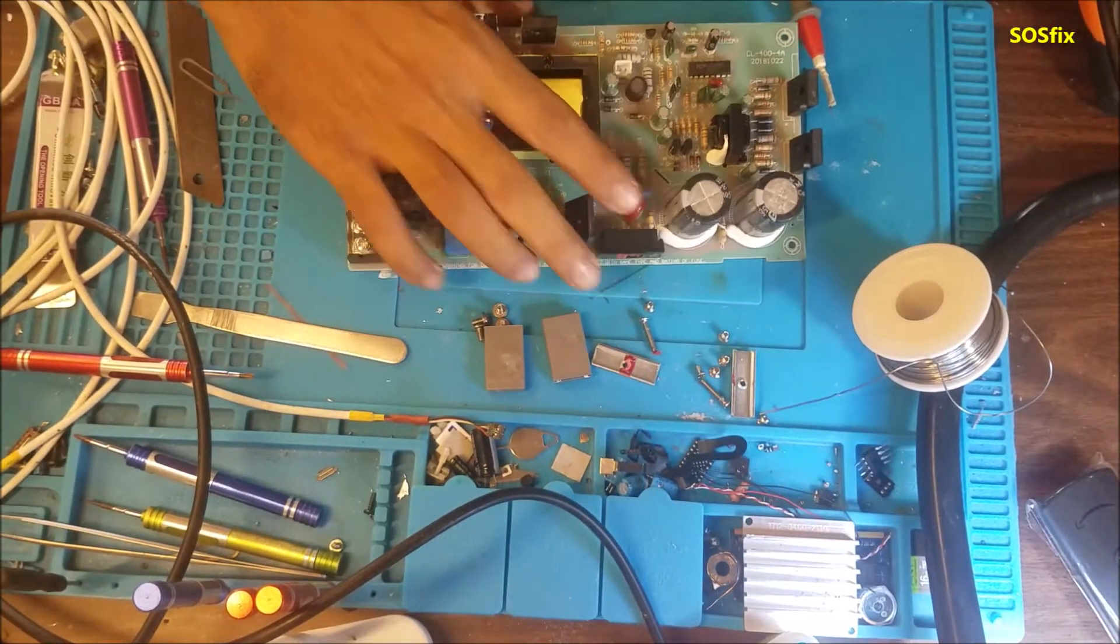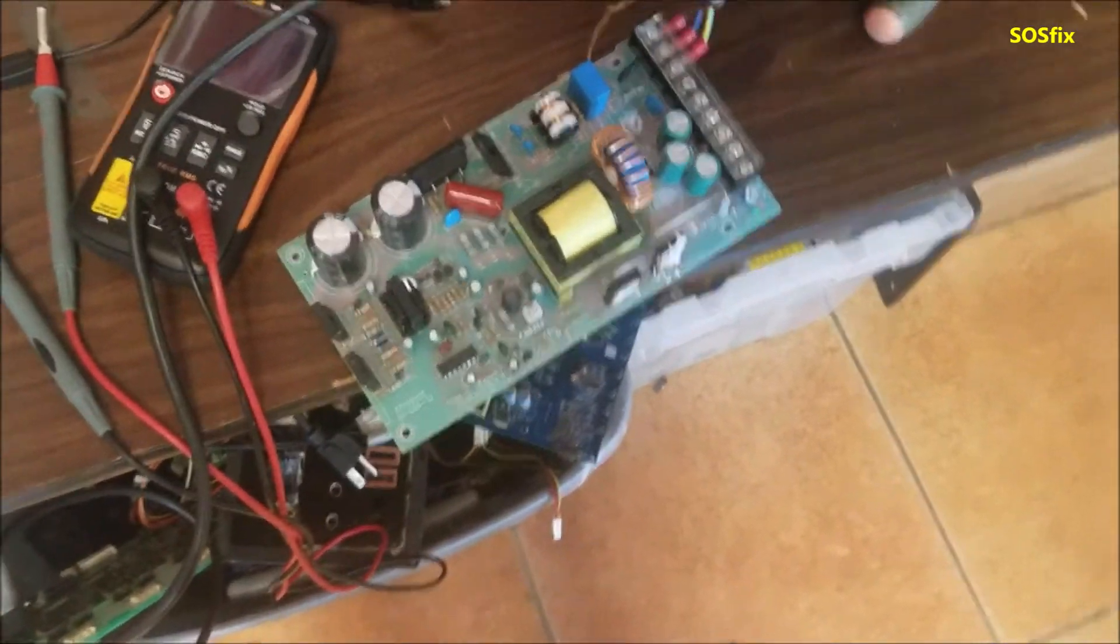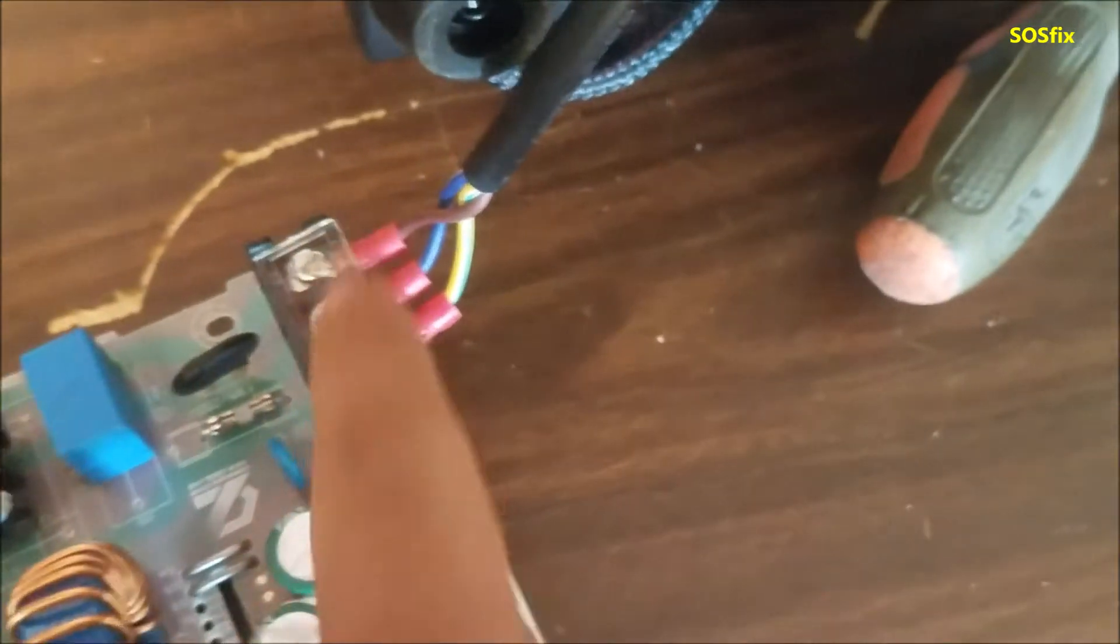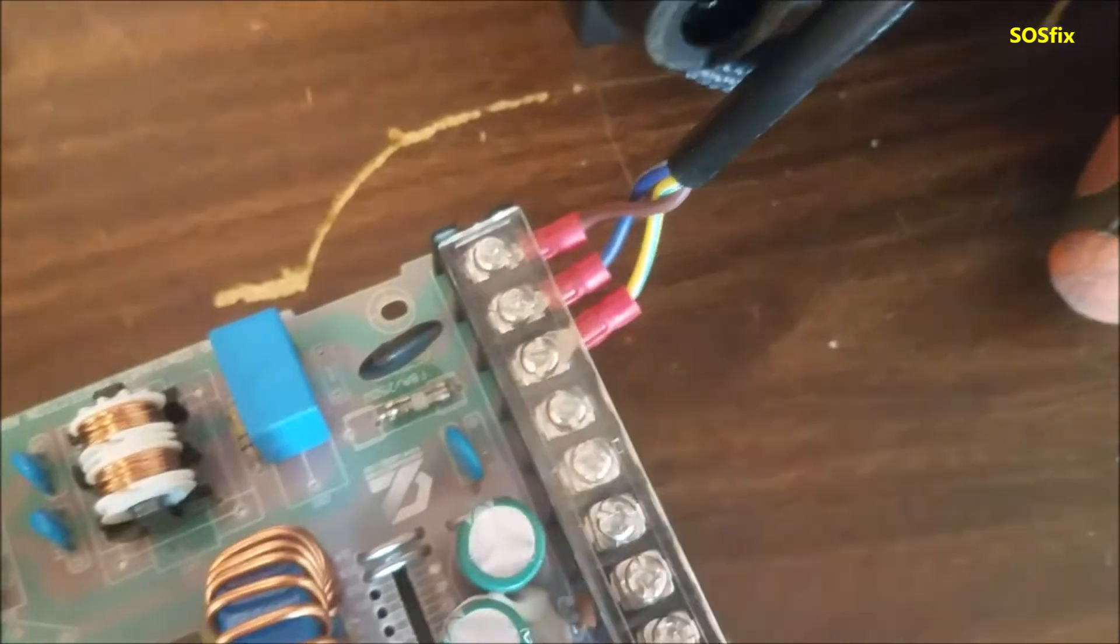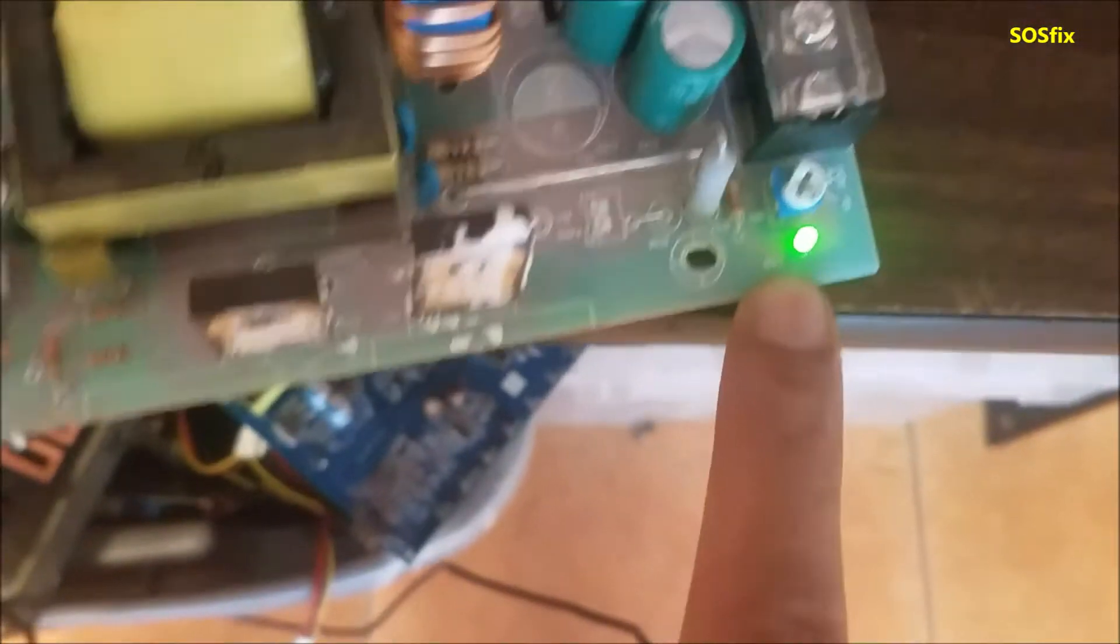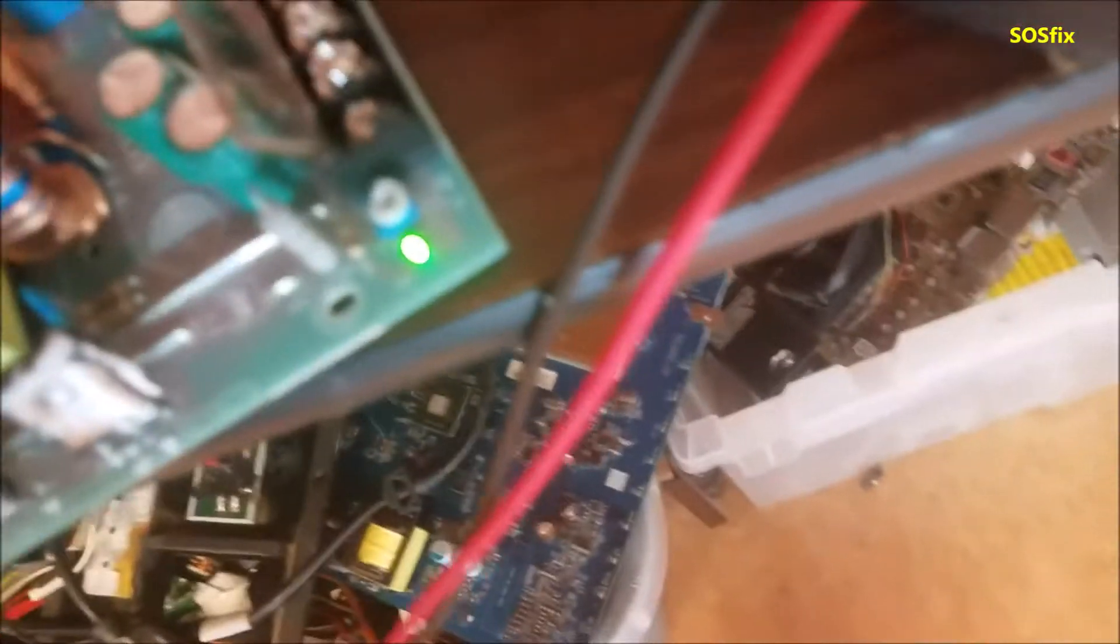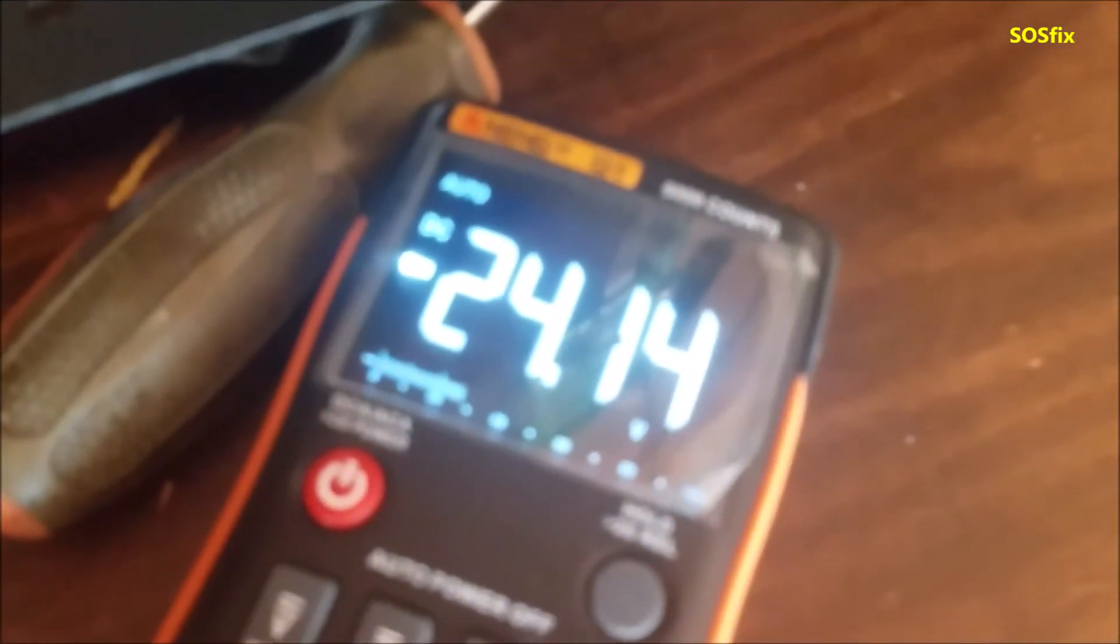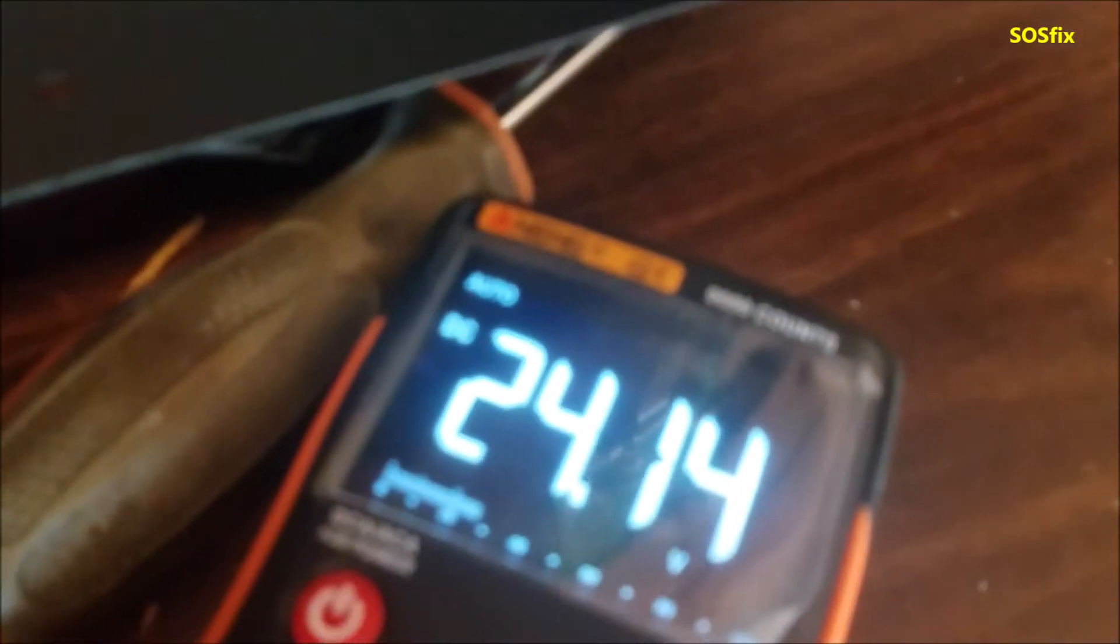Let's test it and see if we can get any power. So I just plugged the power cord, the 110 volt power cord here. So be sure that you don't mix the cords. Let me turn on the power supply, already plugged. And here we have a solid green light. So let's test the output voltage. That's a good change because before it was just flickering. All right, here is 24 volt. You can see it, negative and positive, and here is 24.